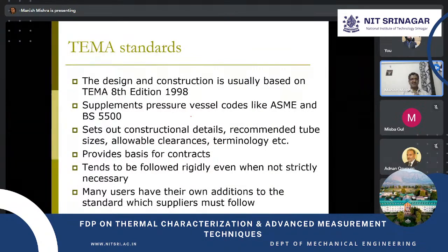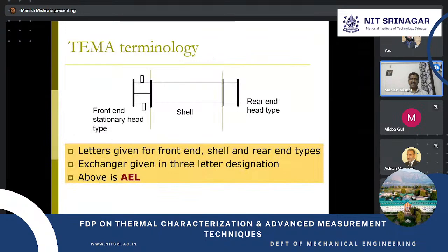Now, for doing all these things, we generally refer to an agency called TEMA, the Tubular Exchanger Manufacturers Association. This is an agency in the US that takes care of design and construction aspects of tubular heat exchangers, covering tube-in-tube, shell and tube varieties, and standardization, similar to BS codes. Based on design aspects, we have nomenclature for front end, rear end, and shell.